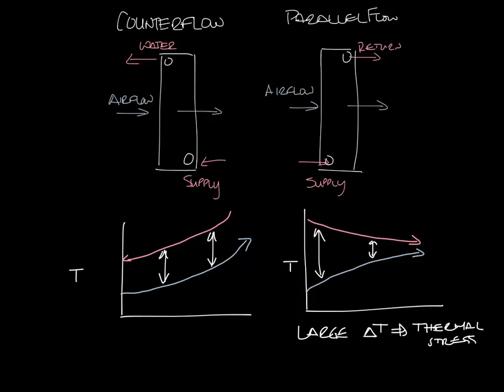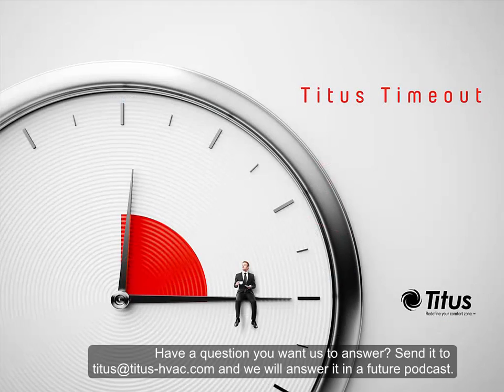Parallel flow coils are good if you're trying to bring the air and water temperatures to nearly the same temperature. But counterflow coils are typically more efficient at heat transfer than parallel flow coils are. So that's the difference between counterflow and parallel flow water coils. Don't forget to subscribe to our YouTube channel, and thanks for taking the time out with us.